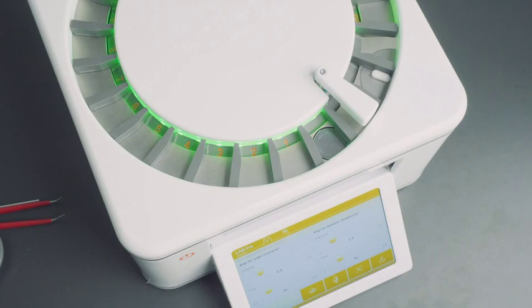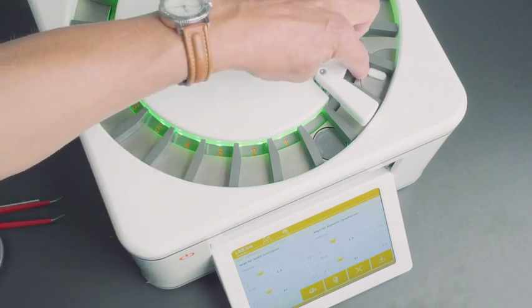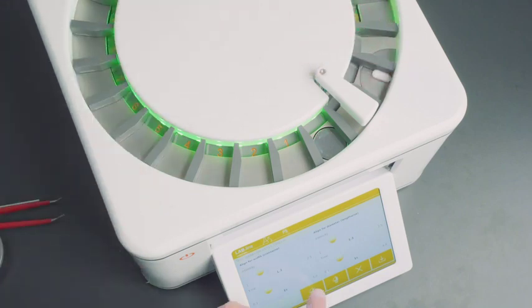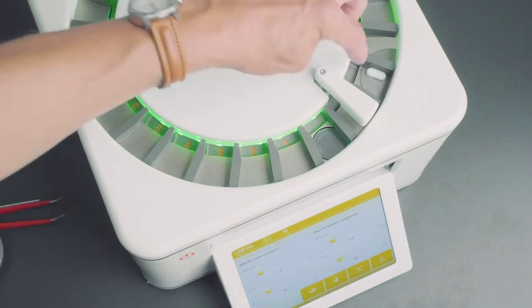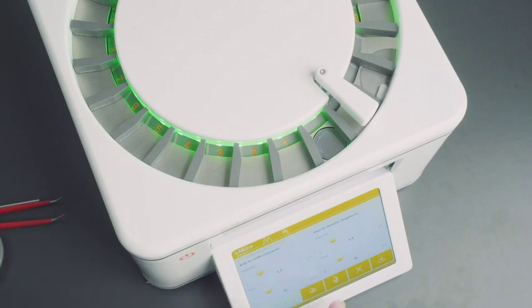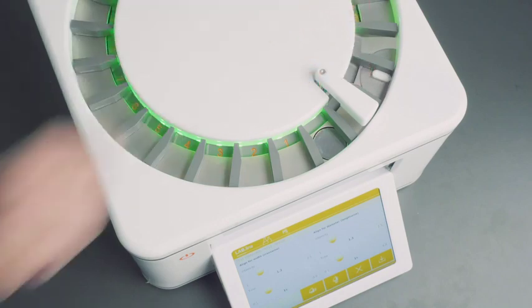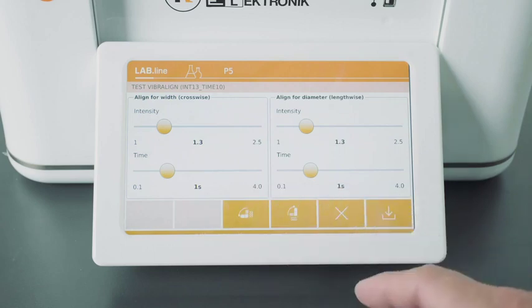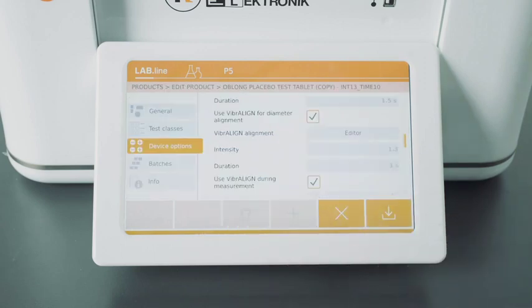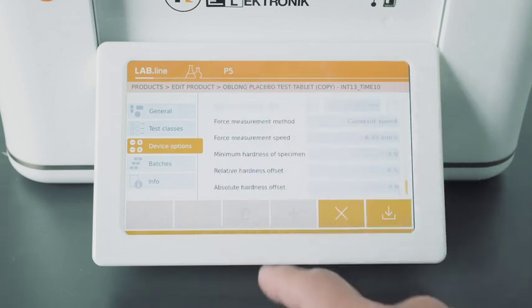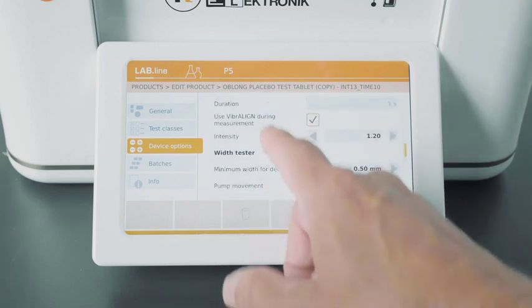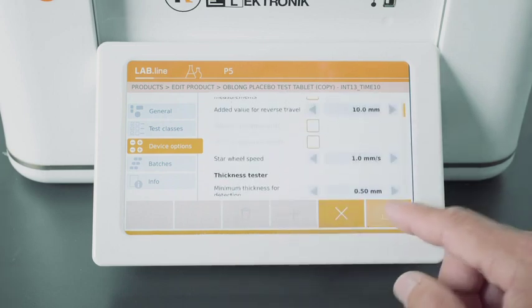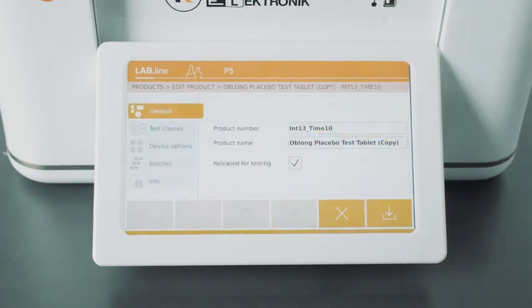Okay, in order to find the right intensity and time, you can use this test mode to turn the tablet and to see how it moves in both directions. To restart, you have to push the tablet back against the fixed jaw of the hardness tester and then repeat the test. So that's fine. This movement is absolutely perfect. Once you find these parameters, you can say store, and these values will be stored to the product. Okay, once you have set up all the values, you say store, and it's finished. Okay, so this was entering the specifications for an oblong tablet.